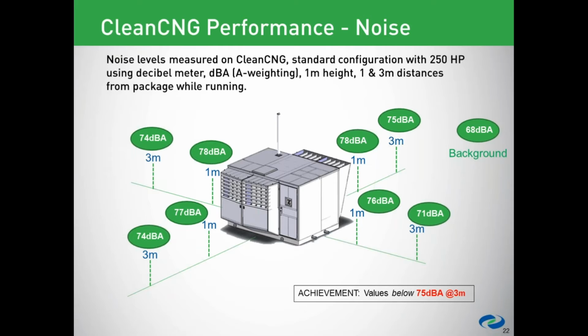In all cases, the noise levels measured even at 1 meter were lower than 80 dBA, and at 3 meters were below 75 decibels. These levels will go up just as a matter of the loss of the sound attenuation measures being removed. One thing to note, though, again, hearkening back to the fact that this is an air-cooled machine. Often you may see measurements on water-cooled machines taken beside the machine with the water-cooled platform elsewhere. These measurements are taken with the full package, including the heat exchanger.